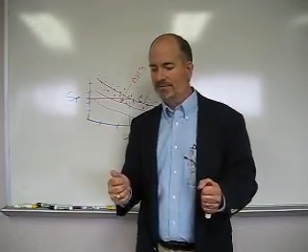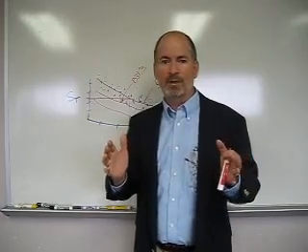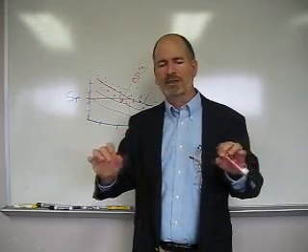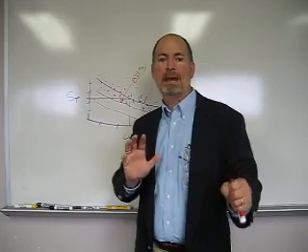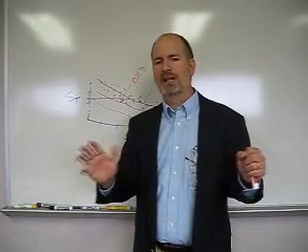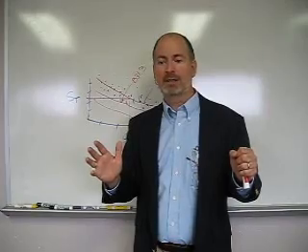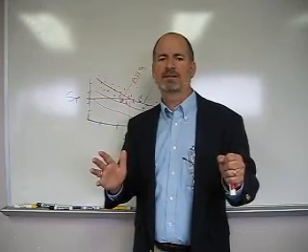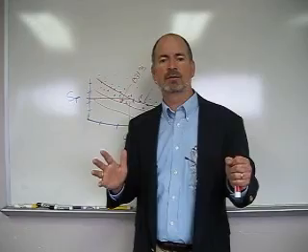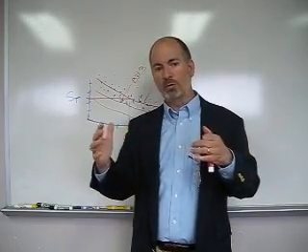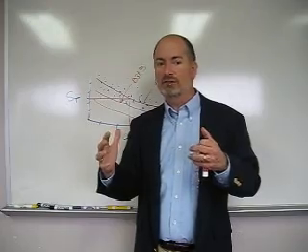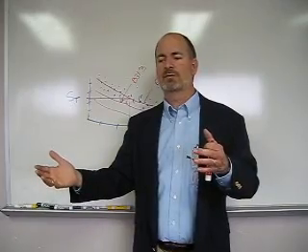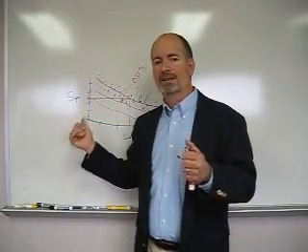Well, the problem is with heat exchangers, people up front put on factors of safety. They've got the tubes, they've got the shell, and they tend to take the max and the min between those and say that's one cycle, which is probably unrealistic, and it's got factors of safety on it right there to begin with. And then they forget about the 200, then they want 7,000, but they want it with the Section 8 curve. It almost is an impossible bellows as it gets so long it becomes unstable, and it becomes more of a safety issue than before. So that's why I'm not a big proponent of this curve.